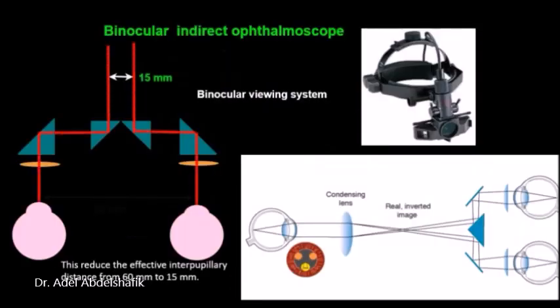Prisms are used as shown in the diagram. This will reduce the effective interpupillary distance from 60 millimeters to 15. This allows the source of light and the two lines of sight of both eyes to get access into the patient through the patient's pupil and this allows binocular vision.